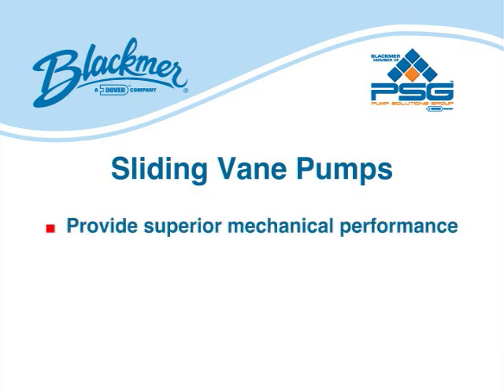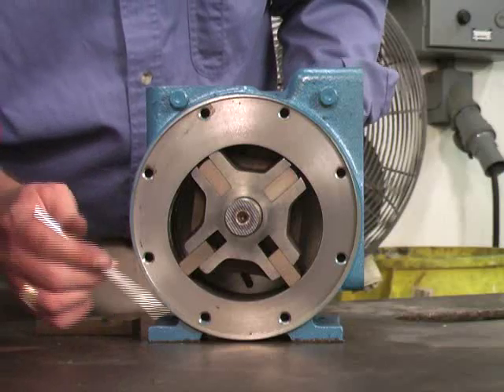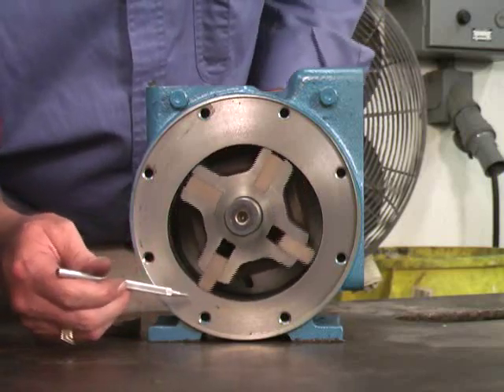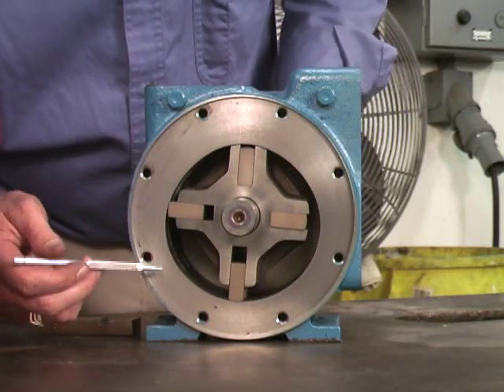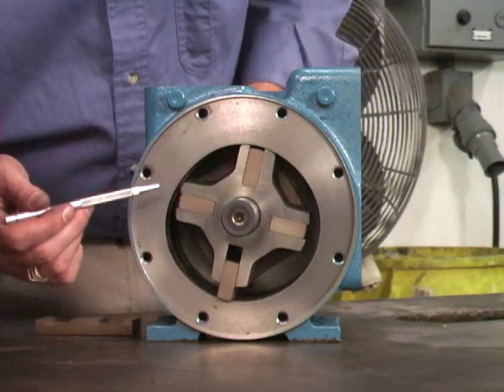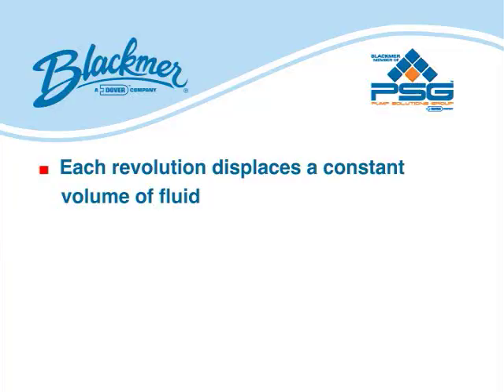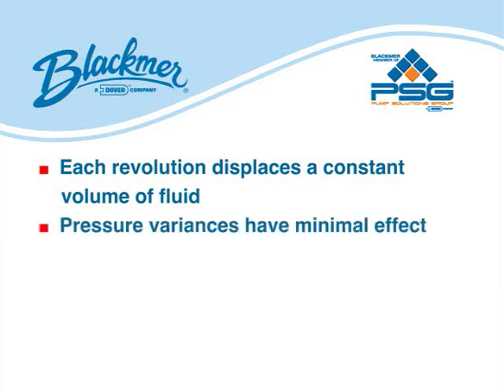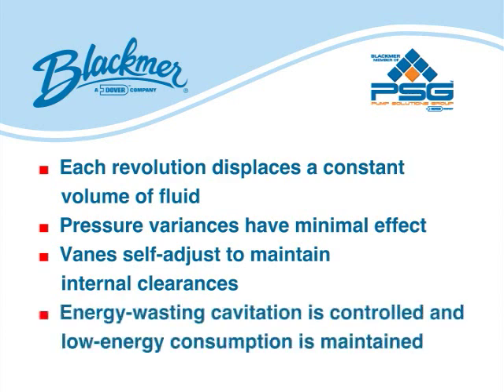Sliding vane pumps provide superior mechanical performance and up to 24% greater energy efficiency than gear pumps. Vane pumps have a number of non-metallic vanes that slide into and out of slots in the pump rotor. When the pump shaft turns the rotor in the pump casing, centrifugal force, rods, and/or pressurized fluid cause the vanes to move outward and bear against the inner bore of the pump casing to form pump chambers. The fluid is passed around the pump casing to the discharge port. Each revolution displaces a constant volume of fluid. Variances in pressure have minimal effect. The sliding vanes self-adjust to maintain internal clearances throughout the operating life of the vanes, controlling energy-wasting cavitation and maintaining low energy consumption.